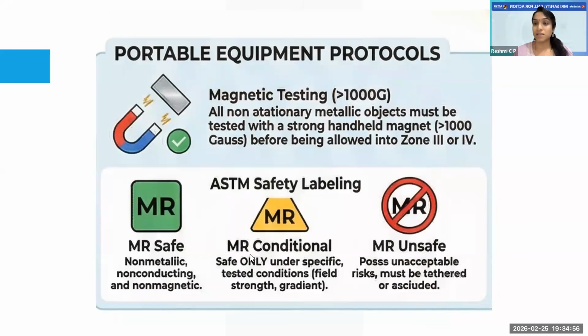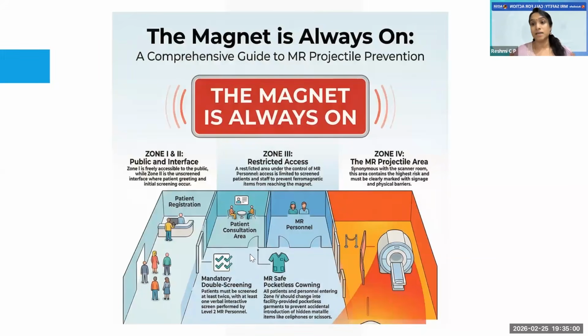Zone 3 is basically the restricted access area or the control room, where there is biometric access. Access should be controlled using either biometrics or a card, so that only screened personnel or MRI staff trained in MR safety are allowed to enter. After that comes zone 4, the area where the MR is being done.